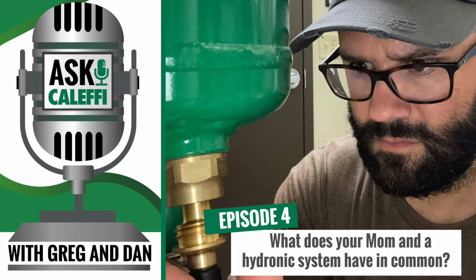That's right. Basically, we're taking an air separator and turning it upside down. You're no longer venting air or separating air. Right. We're trying to pull other things out of fluid. Right, exactly. So, you're going to take that similar, I won't say same, I'll say similar, large-bodied multi-pass device, turning it upside down, having the coalescing mesh inside, and as a multi-pass device, it's going to knock the dirt and debris from the water as it passes through it.